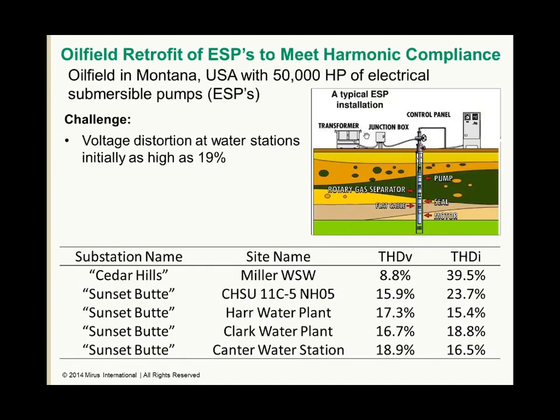A couple of years ago, we were called upon to provide a solution for extremely high levels of current and voltage distortion at an oil field in Montana, which was equipped with 50,000 horsepower of electrical submersible pumps, or ESPs. These pumps are used when an oil field no longer has the pressure to drive the oil to the surface on its own. All models of ESPs use VFDs and therefore introduce harmonic distortion. At this site, voltage distortion was as high as 19% at the various water stations.